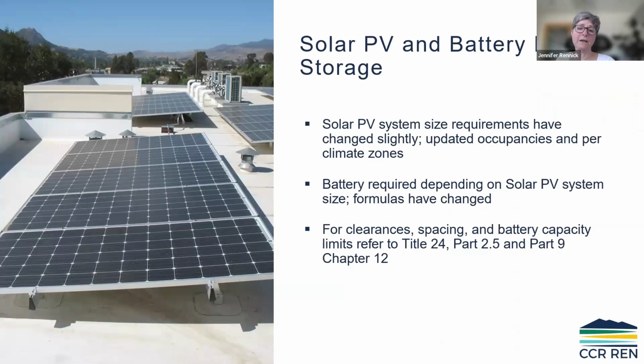For solar PV and battery energy storage, the size requirements have changed, and there are some updates on the occupancy types, and it is by climate zone. The battery requirement really depends on your solar PV system size. The formulas have changed. To understand more about what's changed for clearances, spacing, and the battery capacity limits, you're going to have to go to Title 24, Part 2.5 for the residential and multifamily, but Part 9, Chapter 12 for the non-res.